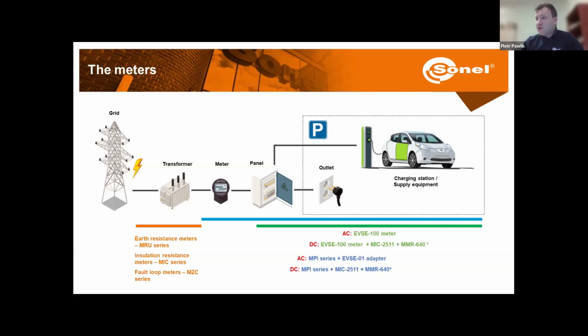Now, for the DC charging stations, we also need some meter for checking SPDs. Here, for example, I can suggest the insulation resistance meter MIC 2511. And to check continuity with 10 amps current, we're going to need a micro-ohmmeter, at least the model MMR 640. Now, further on, in case we would like to check transformers, then we're going to need more powerful single function meters, like one for earth resistance, one for insulation resistance, one for fault loop.